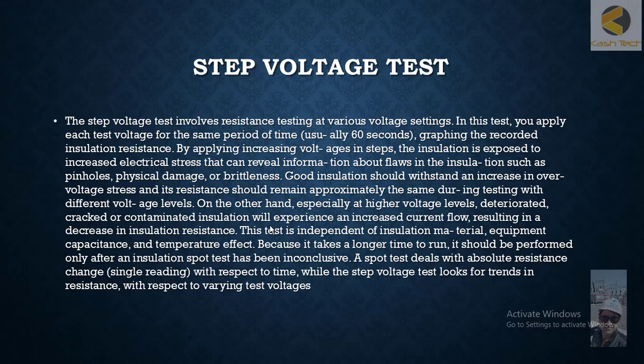Because spot testing is affected by temperature and capacitance value, it's always a good idea to do the step voltage test, which is basically independent of insulation material, equipment capacitance, and temperature effect. This is a very interesting testing technique.